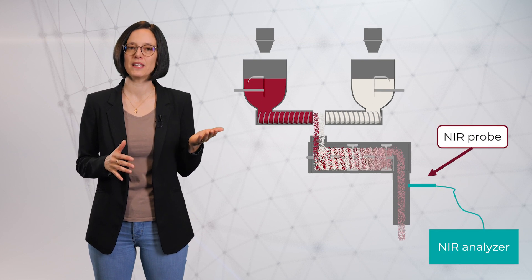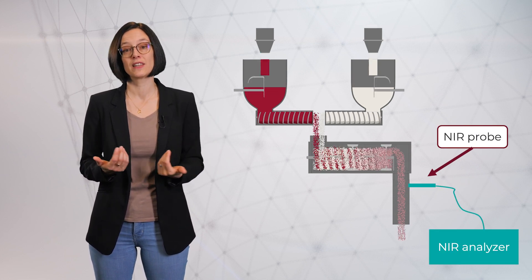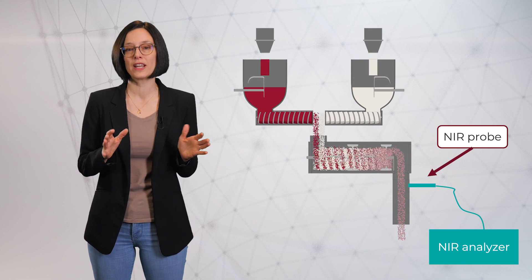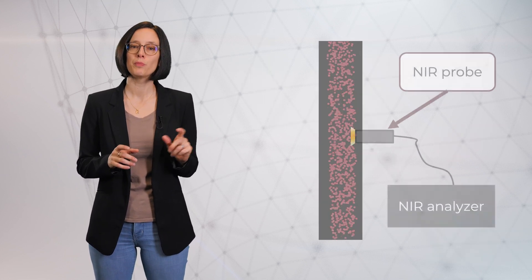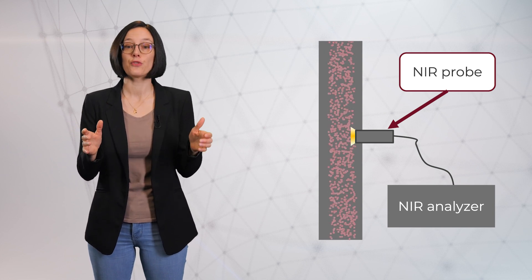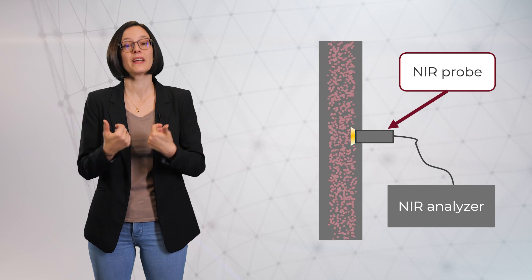Here you see a schematic of an NIR probe installation. An average NIR probe has a diameter in the range of 5 to 10 mm. The probe emits light, which gets scattered on the particles. The reflection is captured by the probe and analyzed.